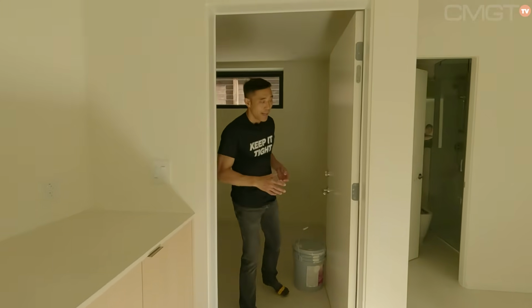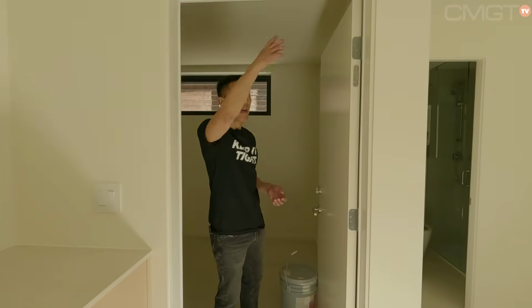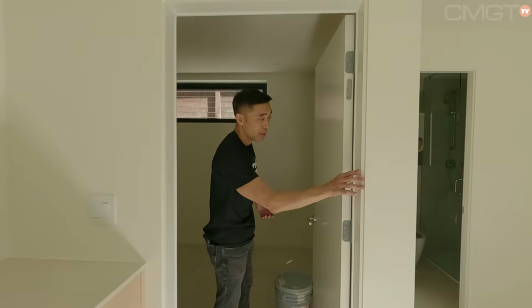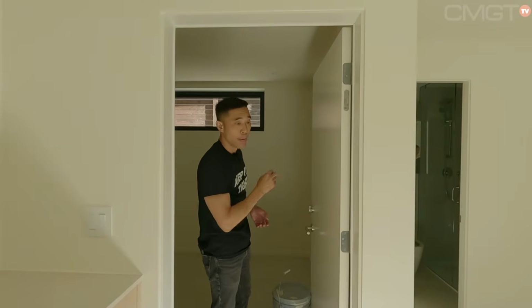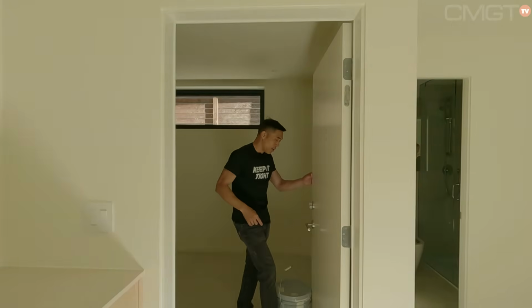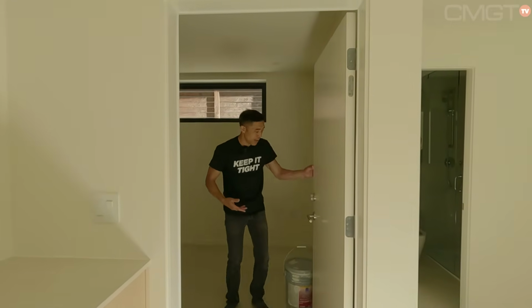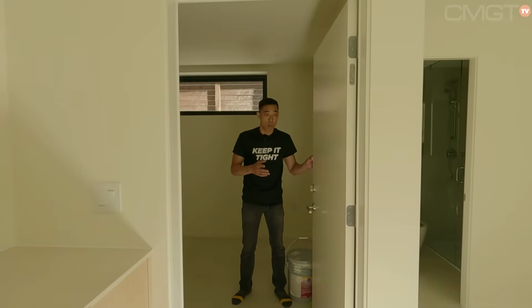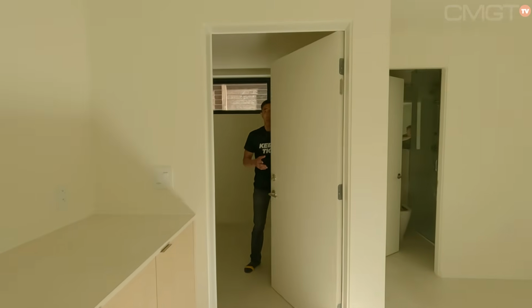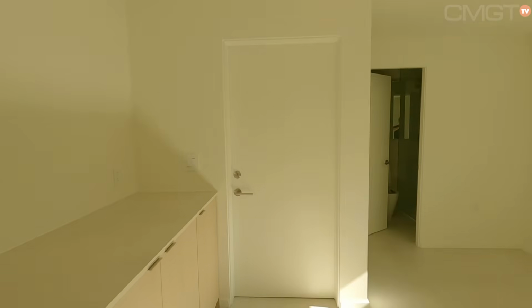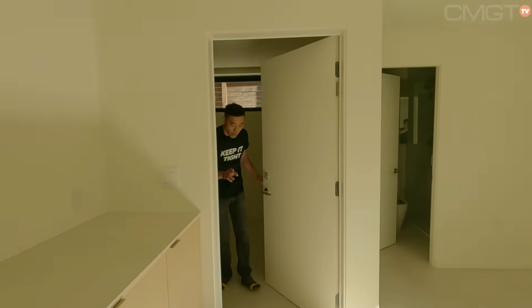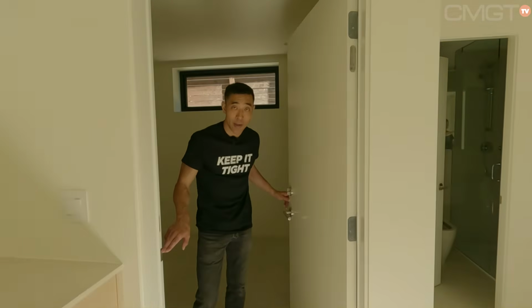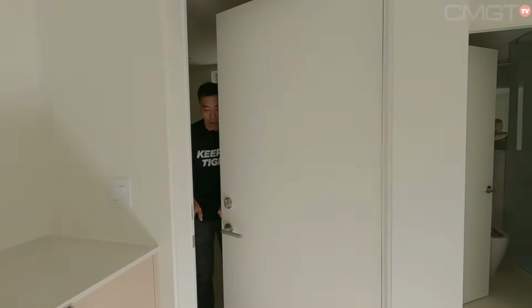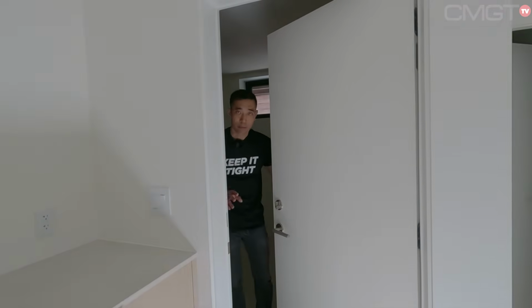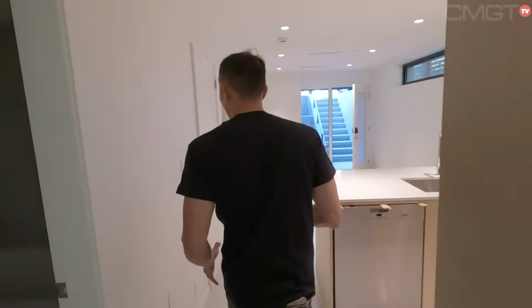One of the requirements is self-closing doors on a fire-rated frame, meaning there are gaskets and a self-closer built into the door. The self-closer is supposed to close the door when released, like so. Inspectors will check that the door latches in place every time. If it just closes like this, unlatched, it will fail.